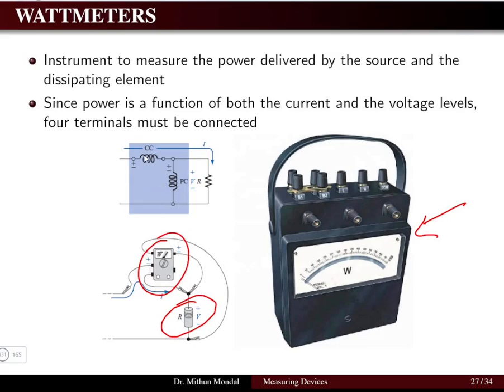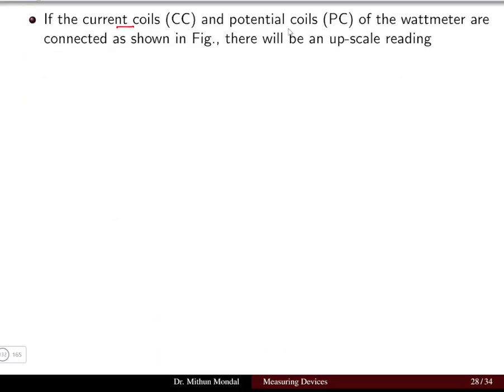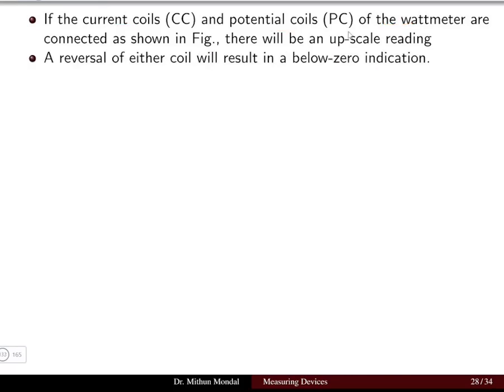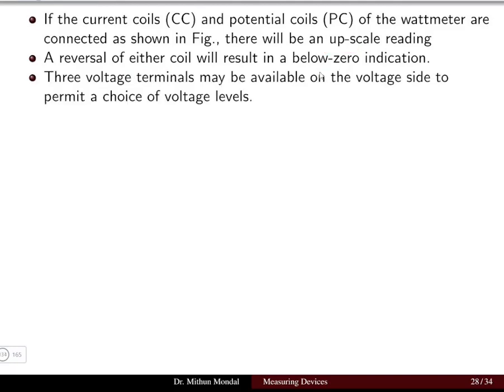The wattmeter has two different types of coils: the current coil and the pressure coil, also known as the voltage coil. When the current coil and potential coil are connected as shown in the figure, there is an upscale reading. A reversal of either coil will result in a below-zero indication, telling you that the connection has to be reversed.